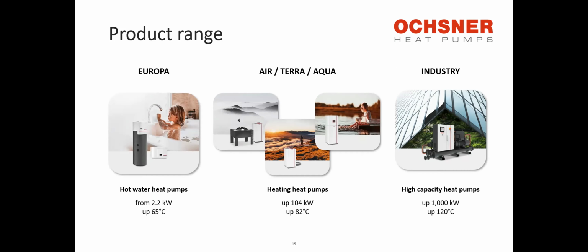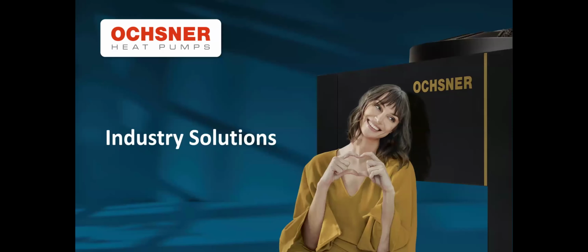And then we come to the more special projects, where I'm the head of this industry part, where we have these high capacity heat pumps up to 1 megawatt. I'm talking in this area about thermal power, so I don't need so much electricity to reach this 1 megawatt. This could also be a good combination for the ORC cycle, for example. But in this area, we're producing heat up to 120 degrees C in specific.